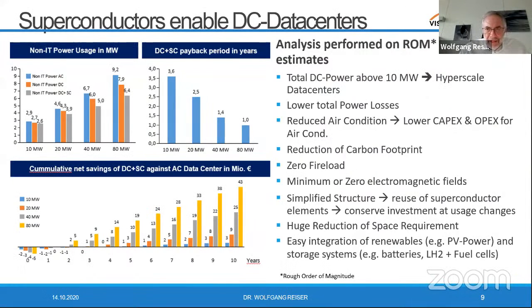We made an analysis based on ROM-based estimates, and what you see in these graphics is that depending on the power of a data center, the return on investment is better, or the net saving increases. So keep in mind: the higher the power, the better it is for DC superconductors. We are coming down to a payback period of around 1 year for 80 megawatts.